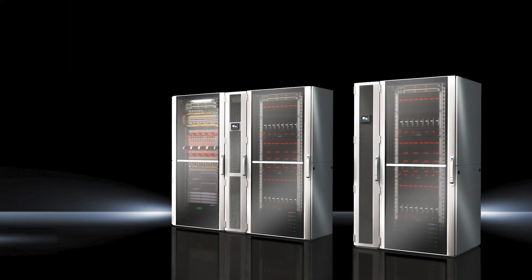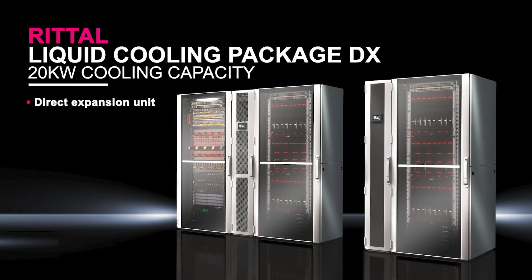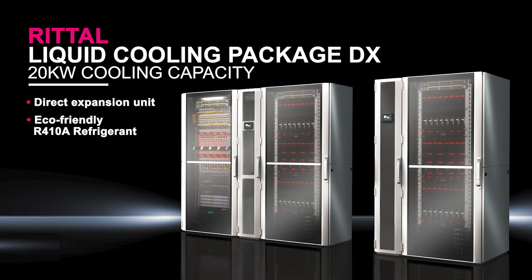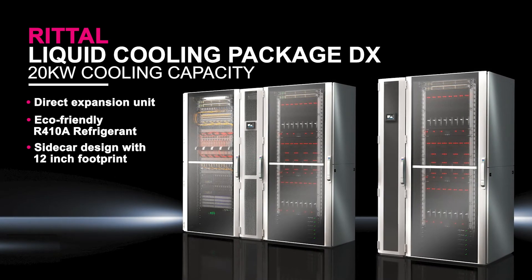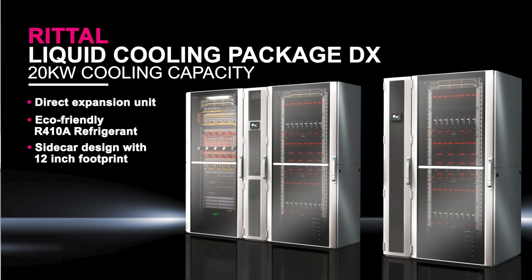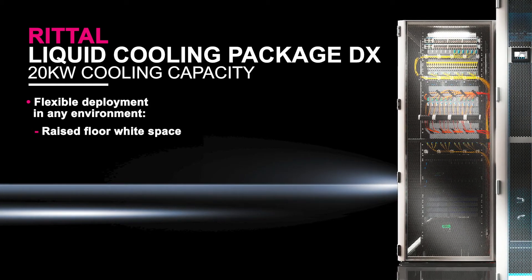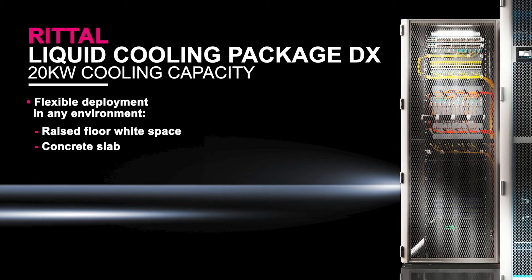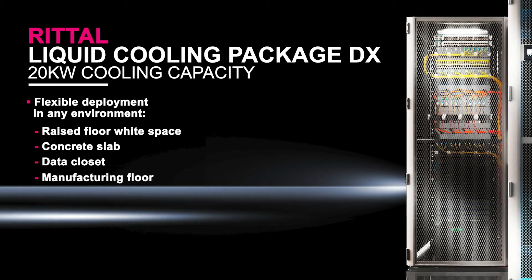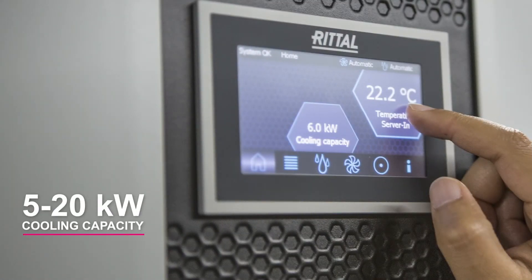One of the most versatile of these solutions is the in-row unit, specifically Rittal's LCP DX 20KW unit, which is a direct expansion unit that utilizes a very environmentally friendly and low-impact R410A refrigerant. It's a sidecar design unit with a footprint of only 12 inches wide. It's ideal for placement within a row or some other constrained space. Its flexibility allows for deployment across virtually any environment you can think of, from the raised floor white space, to a concrete slab, to a data closet in an office environment, a manufacturing facility or plant floor environment, to even a container. And with its range from 5KW to 20KW, it provides a level of future-proofing.